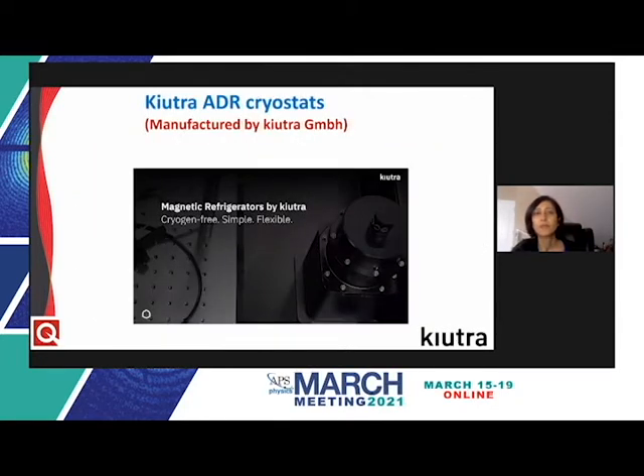Our sub-Kelvin cryostats are manufactured by Kiutra, a spin-off from the Technical University of Munich, Germany. These utilize CADR, or continuous adiabatic demagnetization refrigeration technology, which is based on the magnetocaloric effect. Kiutra's CADR systems offer continuous sub-Kelvin cryogen-independent cooling, and they're compact and can be modularly expanded. They're ideal for fundamental research, including the testing and pre-characterization of quantum materials and devices.